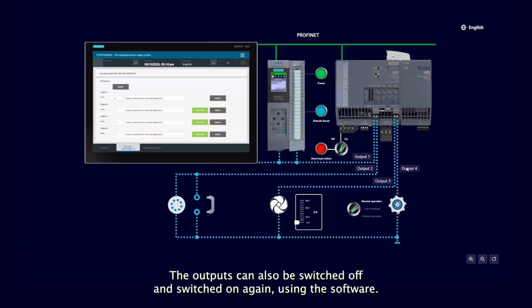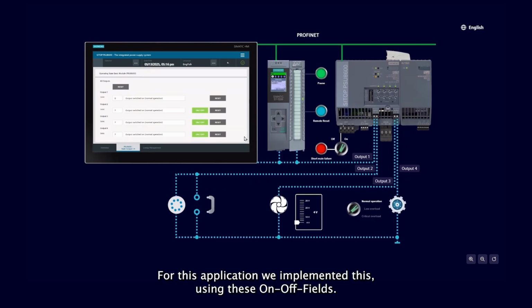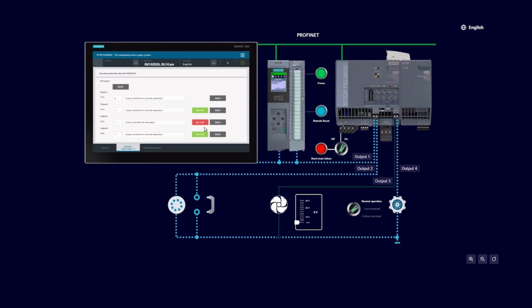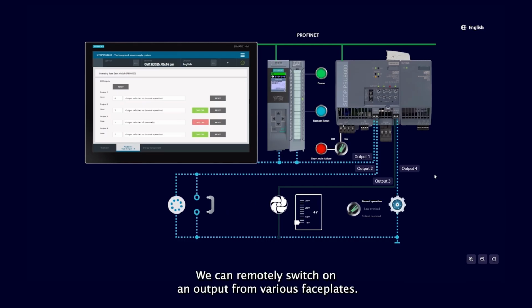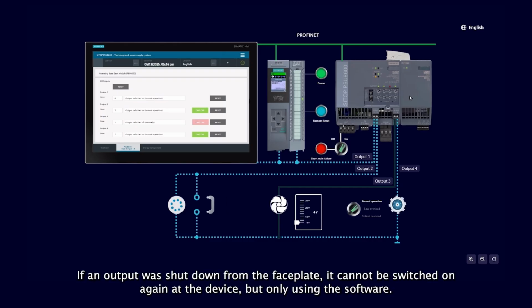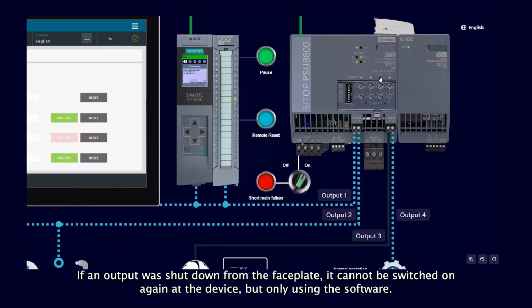The outputs can also be switched off and switched on again using the software. For this application, we implemented this using these on-off fields. The field and the output LED then flash red. We can remotely switch on an output from various faceplates. If an output was shut down from the faceplate, it cannot be switched on again at the device, but only using the software.